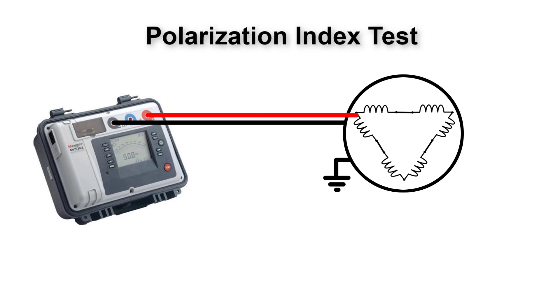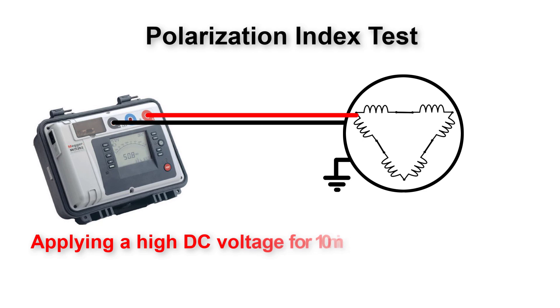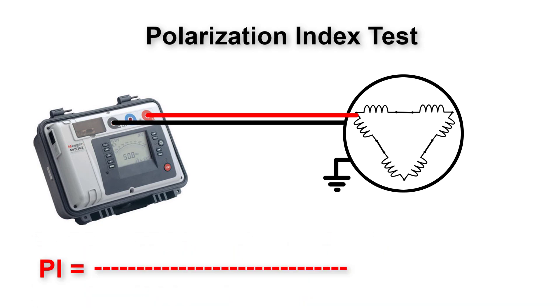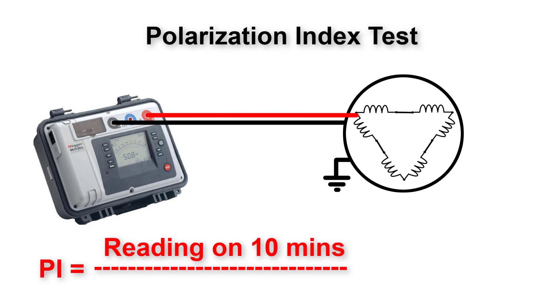The PI test applies the megger test on a motor between its windings and the motor body, but not for just a few seconds. We apply a high DC voltage for 10 minutes and record the readings at one minute and then at 10 minutes. Dividing the reading at 10 minutes by the reading at one minute gives the PI ratio, or polarization index ratio.